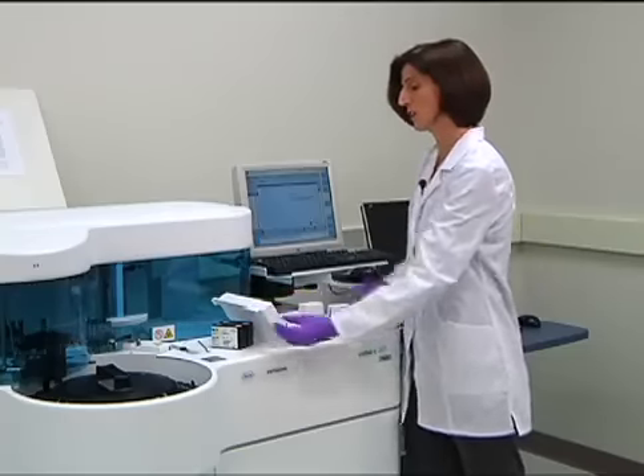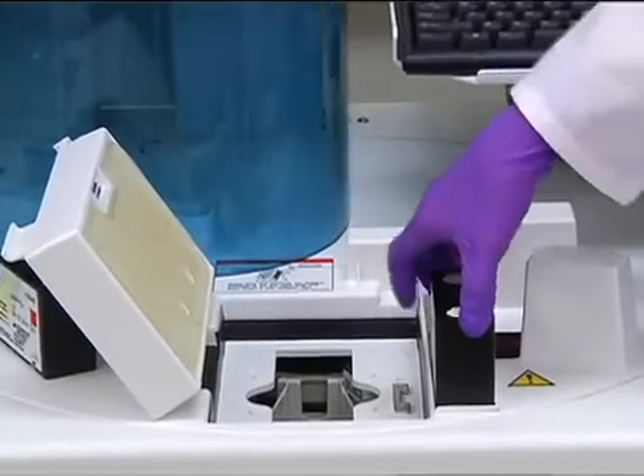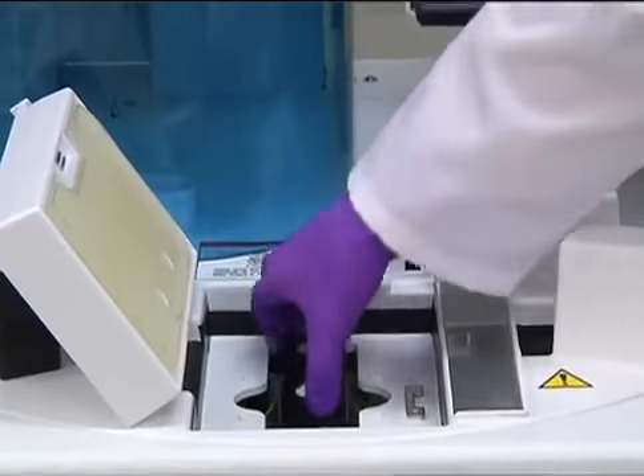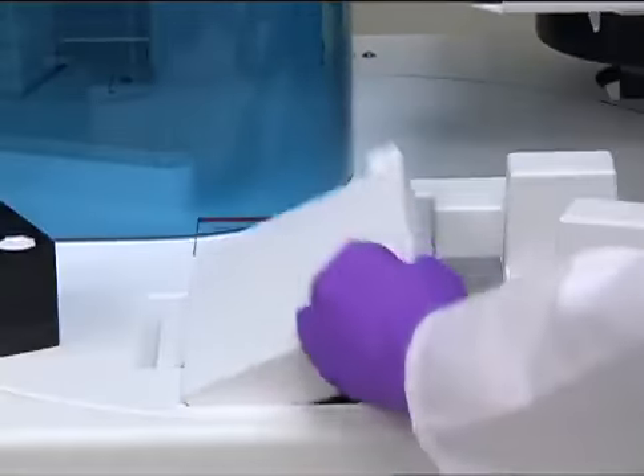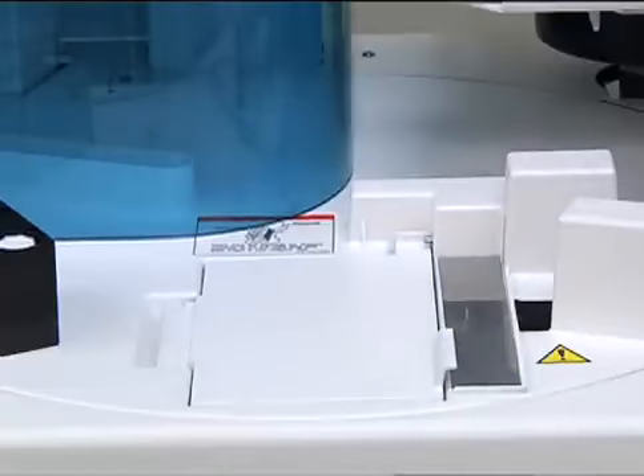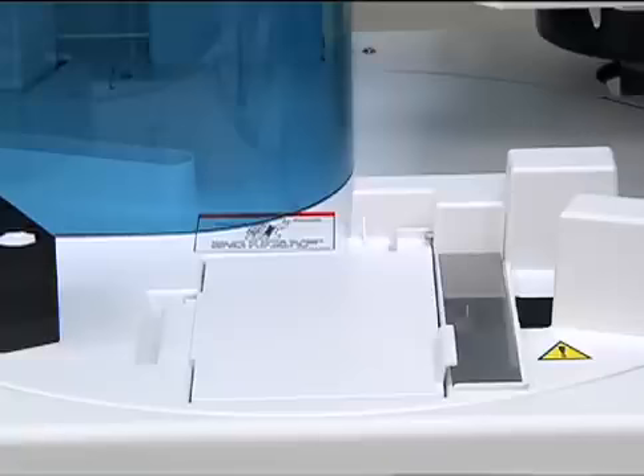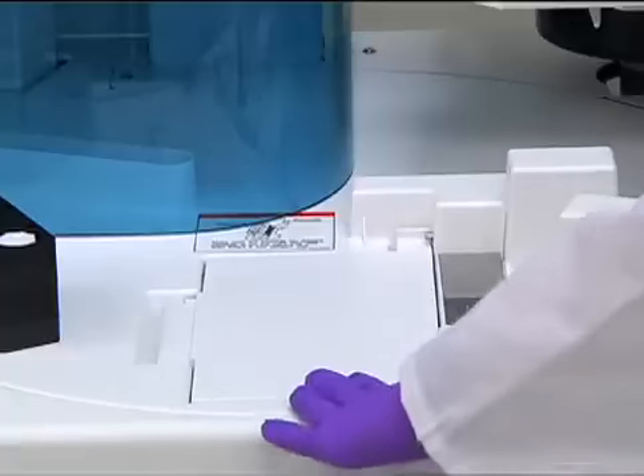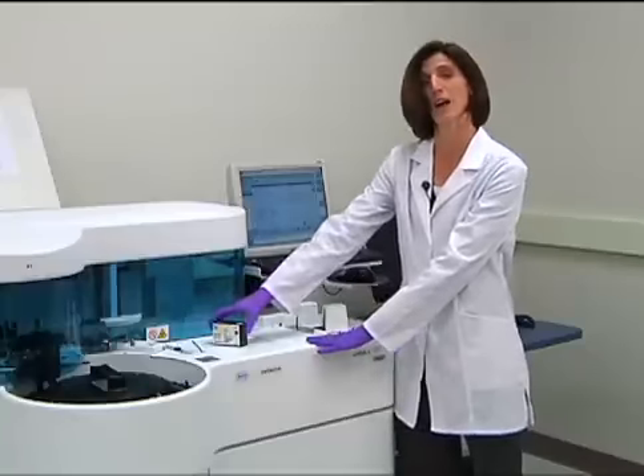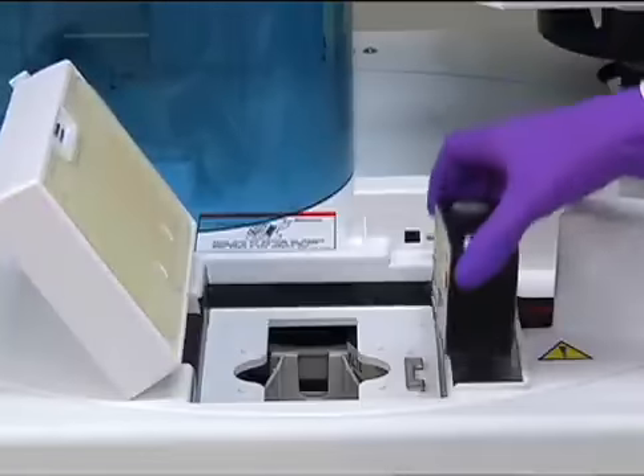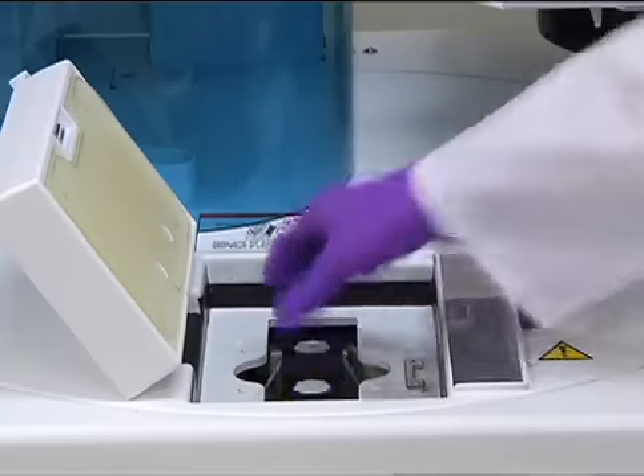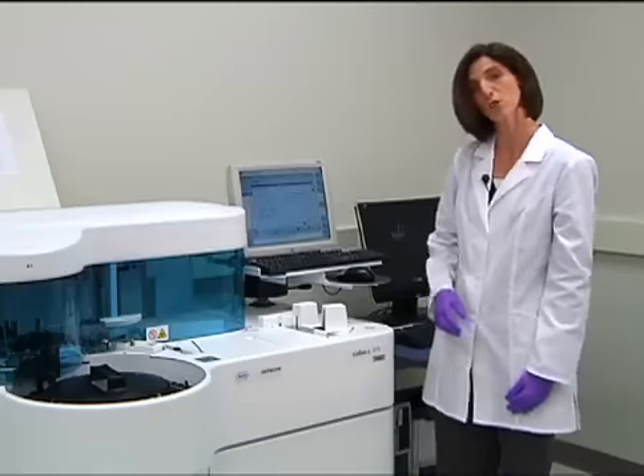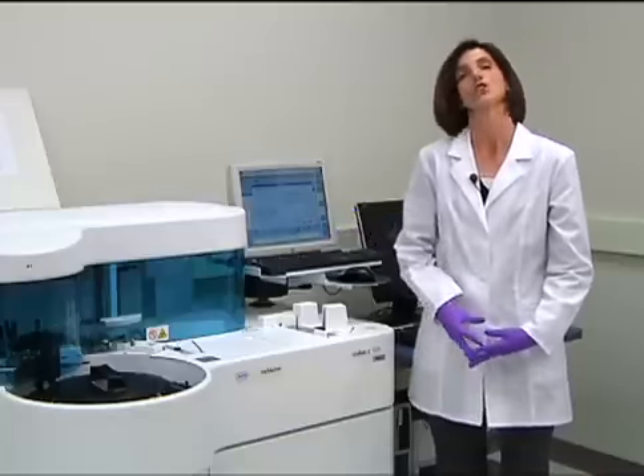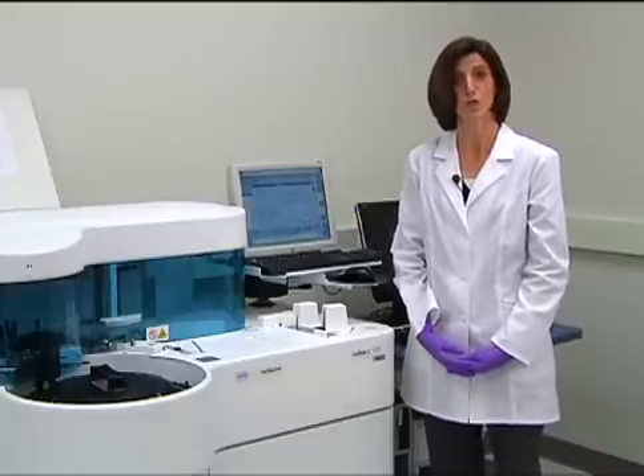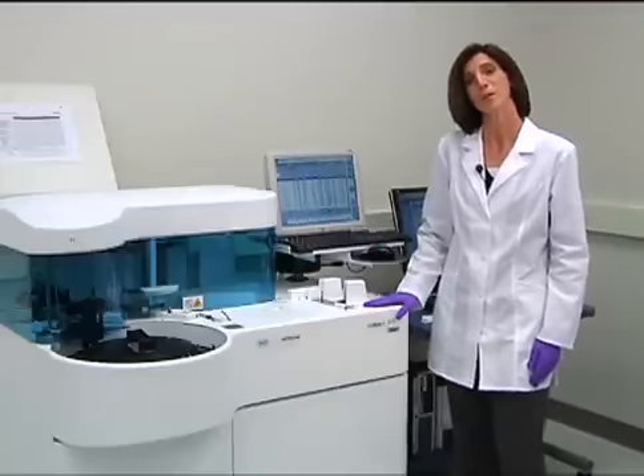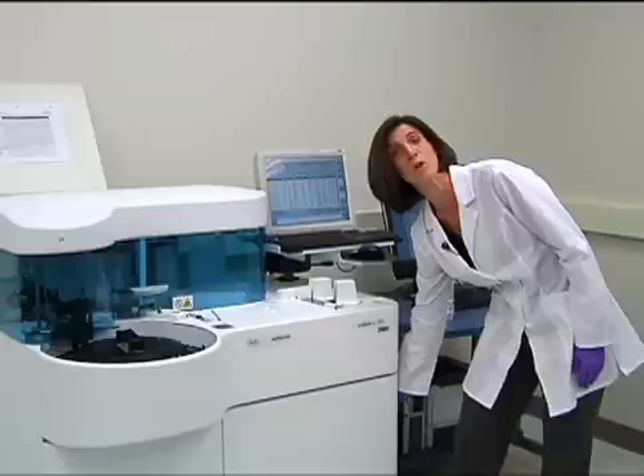We'll simply open the reagent gate and then slide the barcode past the barcode reader and place the pack in the open position. Then we close the gate, and the instrument will take that pack past the sensor to make sure that the pack is loaded. Then it will bring the next available position under the reagent gate, unlock the gate, and allow us to load the next pack. Once all packs are loaded, we will select the End button, and the instrument will automatically pierce the caps and register the pack.